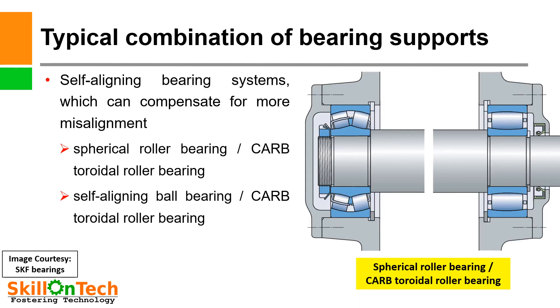Here you can see a spherical roller bearing paired with a CARB toroidal roller bearing — the spherical roller bearing acts as the locating bearing and the CARB toroidal roller bearing acts as the non-locating bearing, providing axial displacement. This is a self-aligning bearing system which can compensate for more misalignments. Self-aligning ball bearings or CARB toroidal roller bearings are used in this configuration.